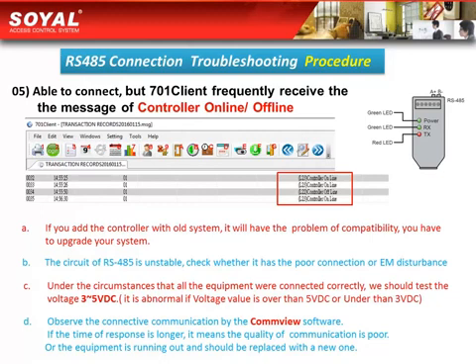Third, under circumstances where all equipment is connected correctly, test the voltage — it should be 3 to 5 volts DC. It is abnormal if the voltage is over 5 volts DC or under 3 volts DC. Fourth, observe the connection communication using the Commview software. If the response time is too long, it means the quality of communication is poor, or the equipment is worn out and should be replaced with a new one.